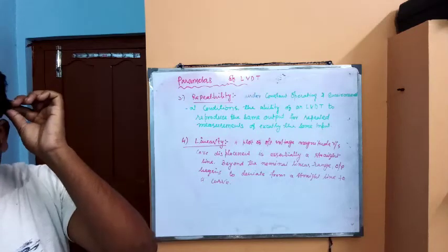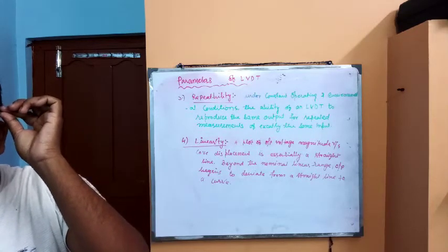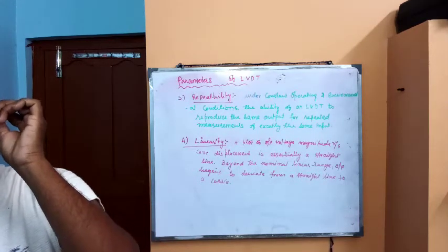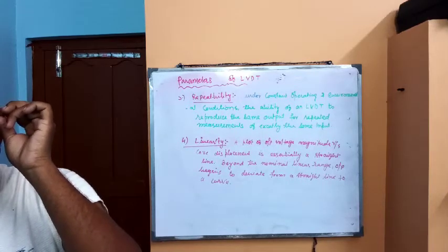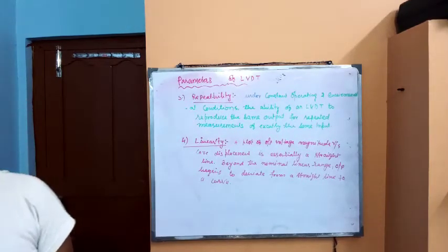The maximum deviation of LVDT output from the straight line is defined as the linearity error, or the non-linearity of the LVDT.